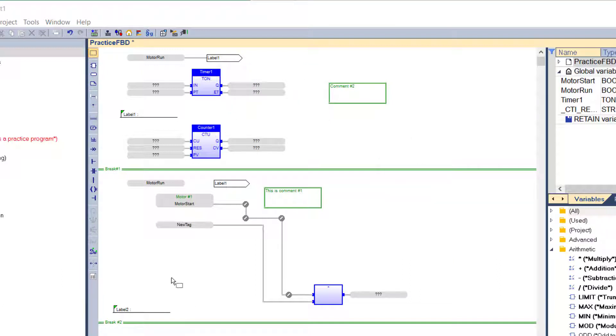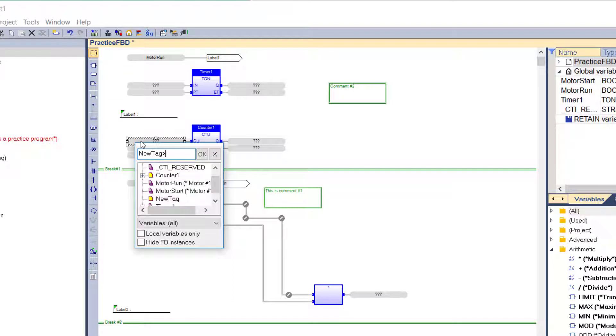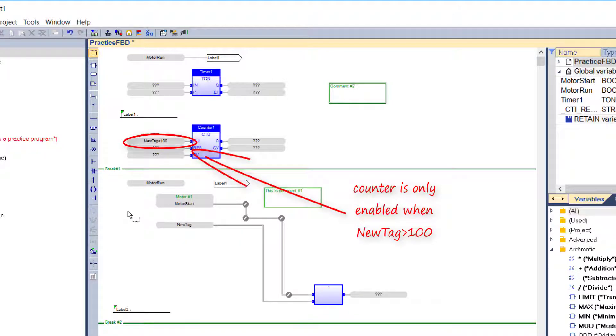Complex structured text expressions can be used with any graphic element in FBD language, making it possible to simplify the diagram when a calculation needs to be entered. The expression must be written in ST language and must fit the data type required by the diagram. For example, an expression put on a contact must be boolean.